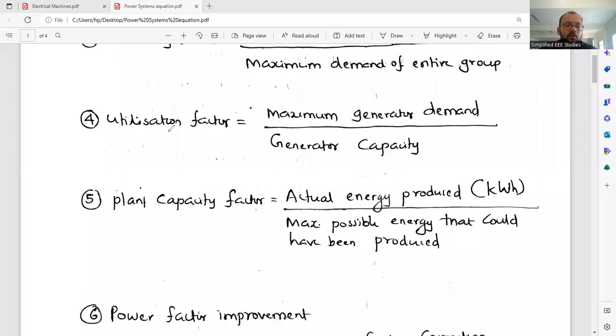Let me continue. Next is utilization factor. What is utilization factor? You need to take the ratio of maximum generator demand divided by generator capacity. Then you will get the utilization factor. Similarly, another important term is called plant capacity factor: actual energy produced upon the maximum possible energy that could have been produced. Kindly note down these important equations. You may get them in terms of a numerical example or in terms of a definition.